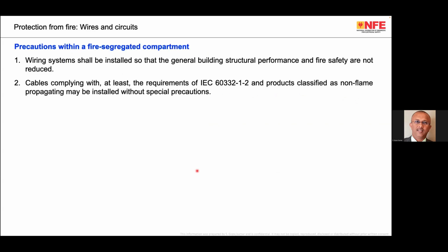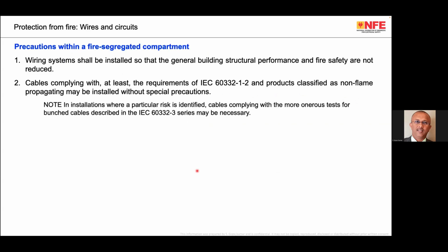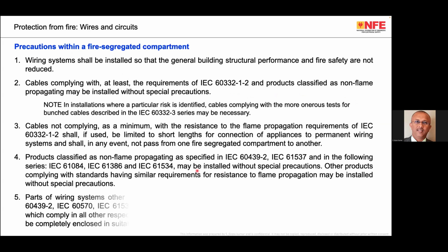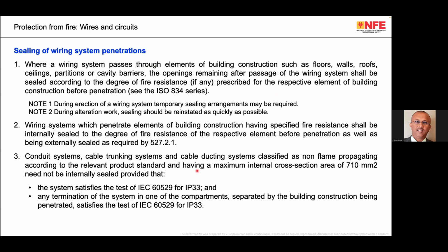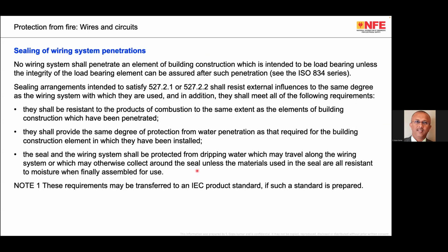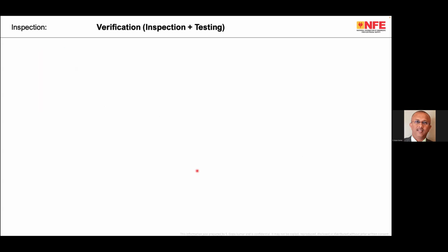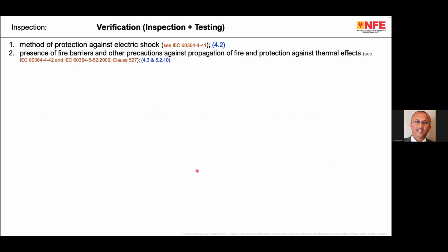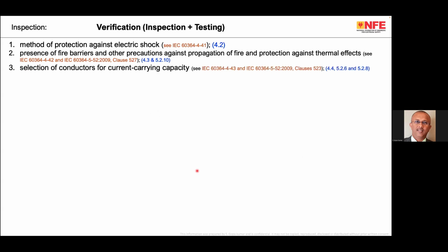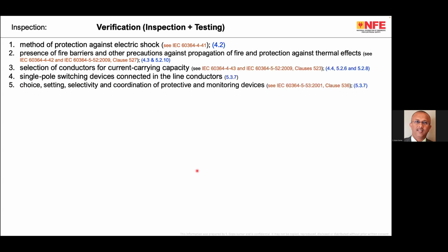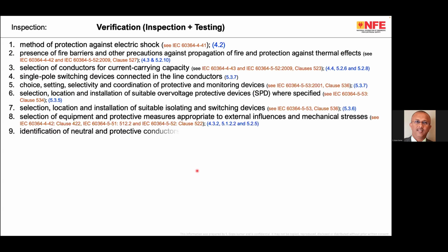Similarly, there are safety measures for fire segregation within the fire segregated compartment. Let me skip this. Sealing of wiring system penetrations. There are different requirements for taking care of the installation. One of the last measures to ensure protection against thermal effect is verifying the electrical installation to ensure that compliance to the standard is made.